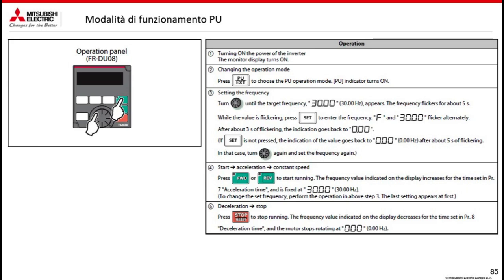But what do you have to do? By means of the dial, which is this thing where the finger is, you will turn clockwise until it reaches the desired frequency. When it has reached the desired frequency, as this example says, for example 30 Hz, you will press set to confirm the desired frequency. An F will appear that indicates that this frequency has been taken. Once you have done this, obviously the screen will return to 0. But why? Because you have not yet given it the start command.